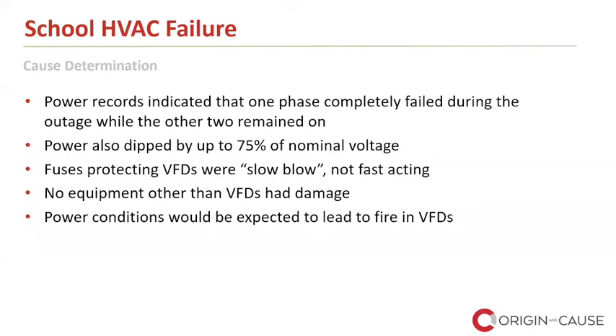The fuses protecting these VFDs were slow blow type, not the typical fast acting. We found that no equipment other than the VFDs had damage, and the power conditions would be expected to lead to failure, heating, potentially fire in VFDs. So VFDs can be damaged if one phase drops to about 80% or below relative to the others. There were also wild fluctuations over time. This was a power outage that sort of came and went with large fluctuations in power. So it is possible that ordinary fast acting fuses might have protected these VFDs.